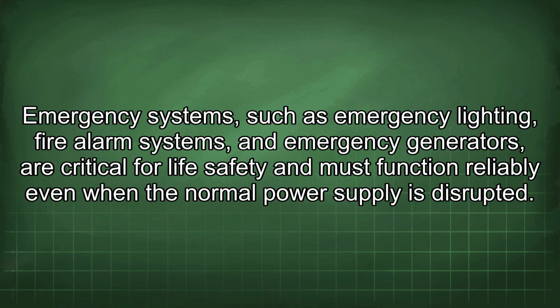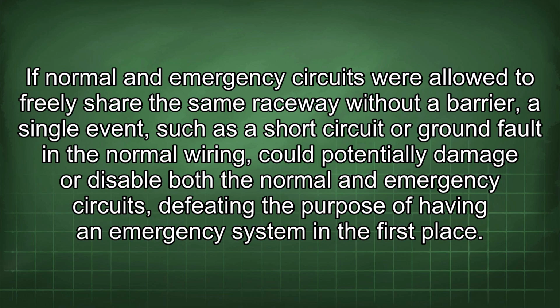Emergency systems such as emergency lighting, fire alarm systems, and emergency generators are critical for life safety and must function reliably even when the normal power supply is disrupted. If normal and emergency circuits were allowed to freely share the same raceway without a barrier, a single event such as a short circuit or ground fault in the normal wiring could potentially damage or disable both the normal and emergency circuits, defeating the purpose of having an emergency system in the first place.